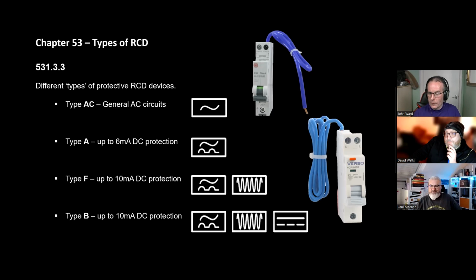Type A, which is really the minimum one you want to be looking at, offers up to 6 milliamps of immunity protection from DC leakage. Type F offers up to 10 milliamps, and it gives obviously a multitude of frequency protection, because obviously a lot of this stuff has frequency converters in it now.